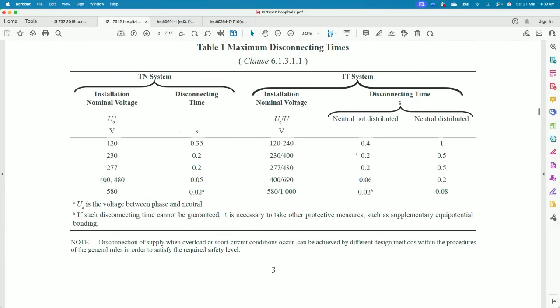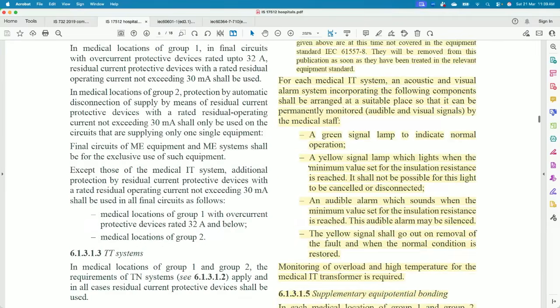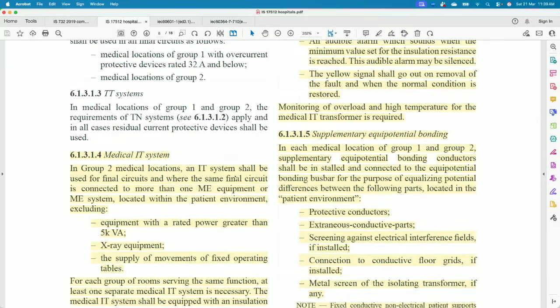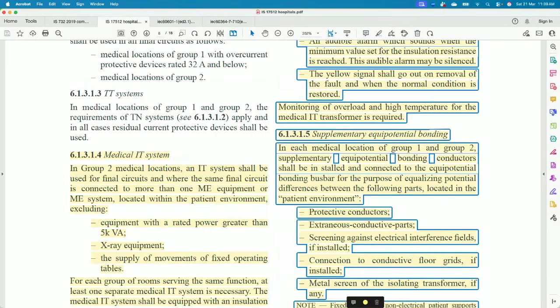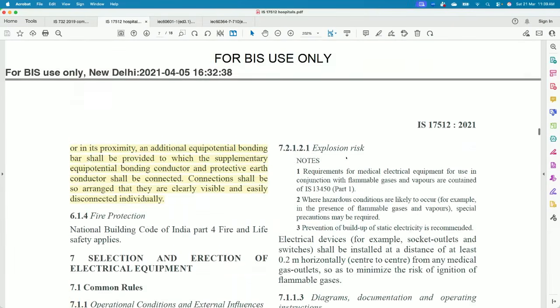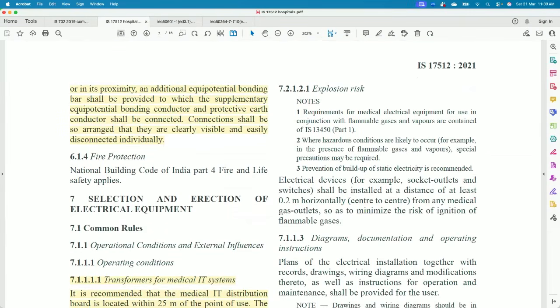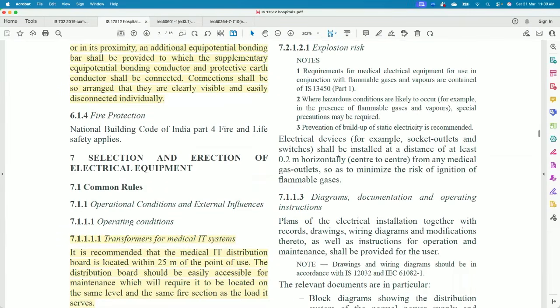The disconnection time has to be limited to less than what you are seeing in the table, maybe 0.4 seconds, 0.2 seconds, and so on. So then you need a medical IT system. You need a supplementary equipotential bonding. So all these measures are very much essential.